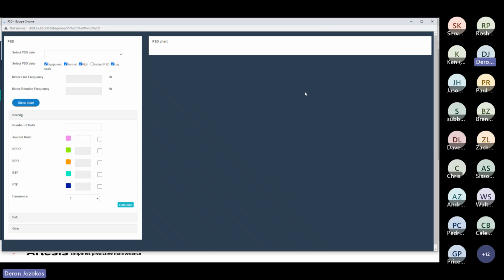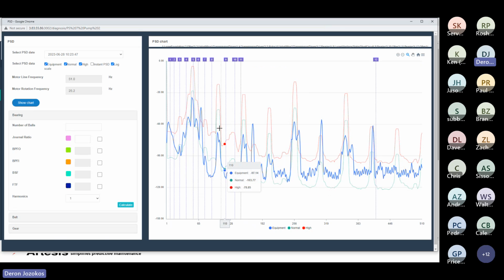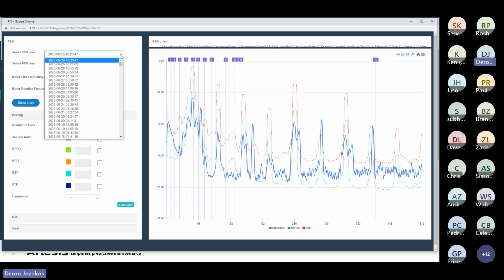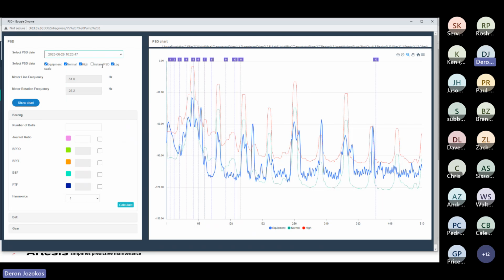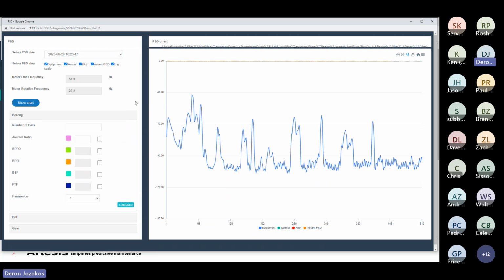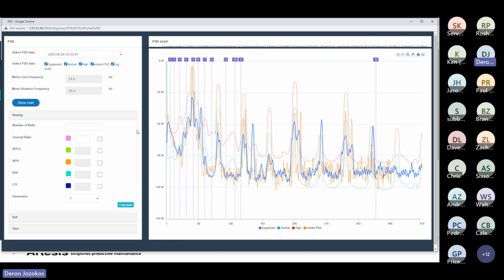The PSD is our power spectral density. It's a more stable version of the FFT and more accurate, using electrical signature analysis in the model base. So we give you a reference of what it saw during the learn, and we take a new spectrum every 10 hours by default. That's adjustable if you need it, but by default, 10 hours is definitely plenty of spectrums to see changes over time, and you can plot those out. Right, so it's like going out and taking a new vibration spectrum every 10 hours.